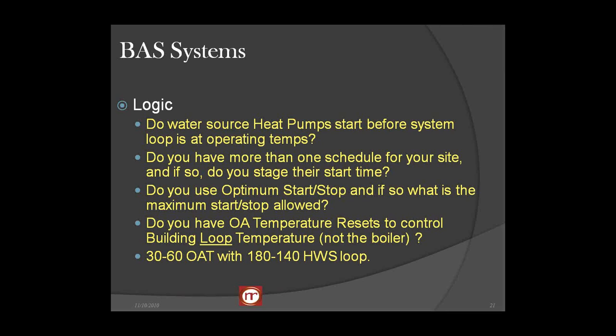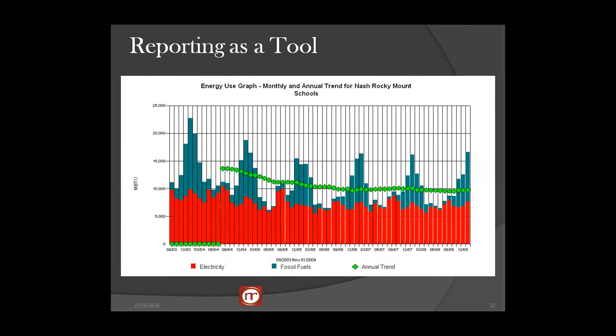And that's kind of just a starting point. You might have to change it differently if you're in Maine, let's say. Or if you're in Florida, you might can get a little more creative. The thing to watch here is don't try to do this with the boiler. Unless you have what is called a condensing boiler, and you set that loop supply below 140, the boiler will condense, and that will cause damage to the boiler and shorten its life.